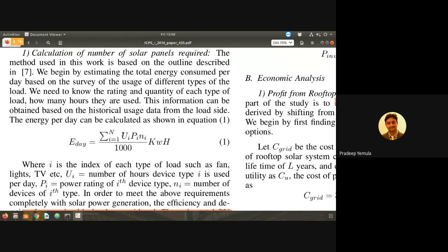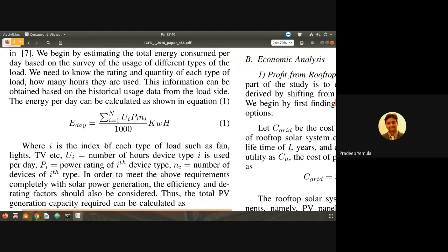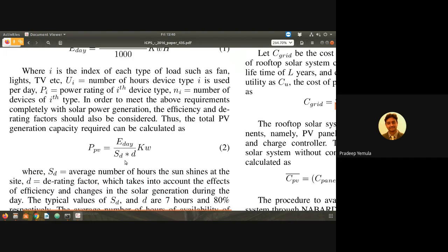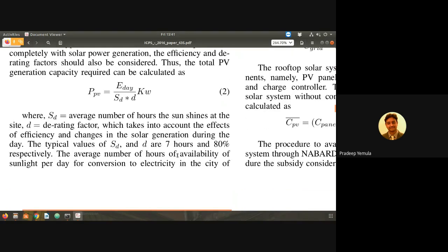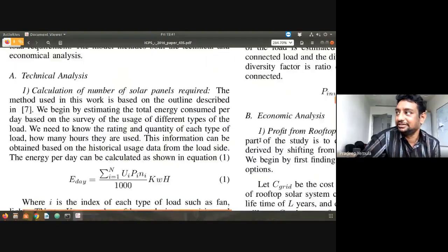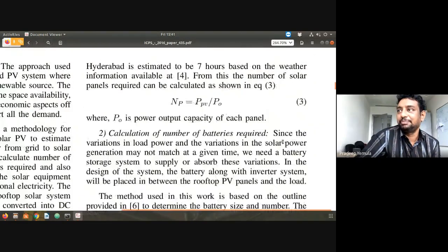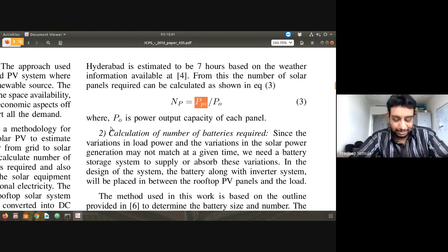Your total power output of PV should equal energy per day divided by average sun hours multiplied by the de-rating factor. Typical values are seven hours of sun and 80% de-rating factor. From that, we can calculate PPV — the power rating. Here the calculation shows eight hours of sunlight and 80% system efficiency are taken, giving a capacity of 7.8 kilowatts.